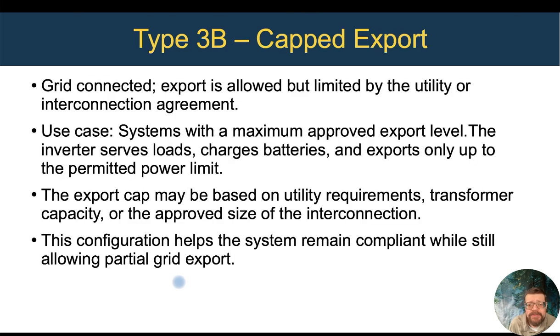Type 3B is very similar to a 3A, only we can export some to the utility, just not the full amount of our PV array or inverter size. This might be the utility requirements. Sometimes if you've got a really large system, the utility may say you've only got a 15 kVA transformer. So if you put in a 25 kilowatt system, you can't export more than 15 kilowatts to us because we're worried about our transformer capacity.